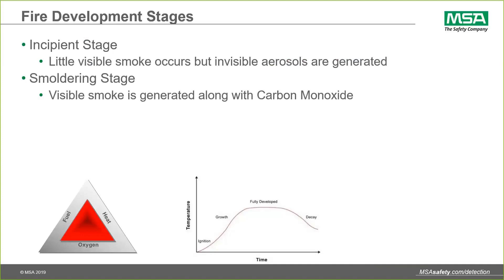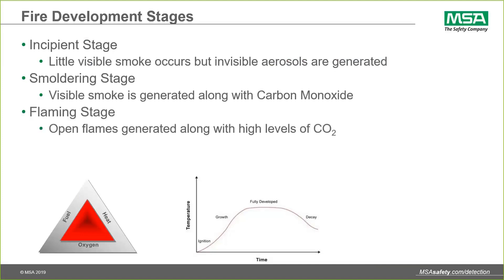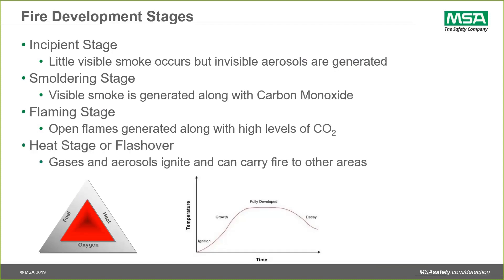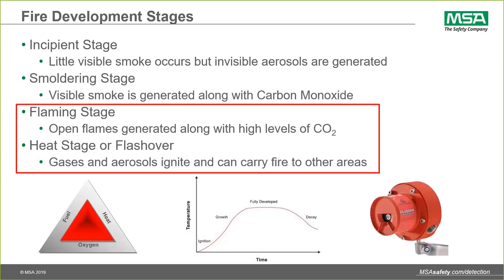We don't have a fully developed flame yet, which comes next. Now we have a flaming stage where you've actually got an open fire, open flame with high levels of CO2, and then eventually the heat stage or flashover. Now we've got a lot of heat and aerosol — so much heat from this flame it could actually carry the fire to other areas. It's the flaming and the heat stage where an optical flame detector is actually applicable.